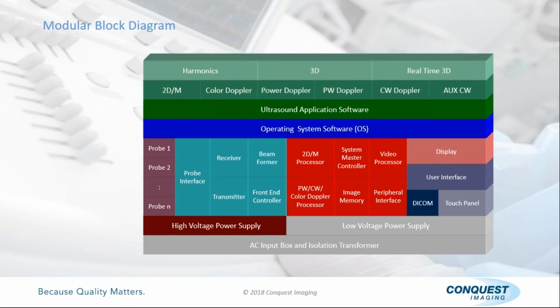And this is what it all looks like when it comes together. Okay? So again, if you just look at it, you have your voltage, your power supply subsystem, your front end that we just broke down, your back end, which is your Windows computer. But in addition to that, it has your Windows software, your application software, your options are loaded on, and your functions. What can the system do? When you see 2D, Doppler, power Doppler, pulse wave Doppler, continuous wave Doppler, all those functions are what's built into the system. You can't change them. If I was to hit this mode button, it would give the list of modes that this system can do. Well, that's them. You can't change it.